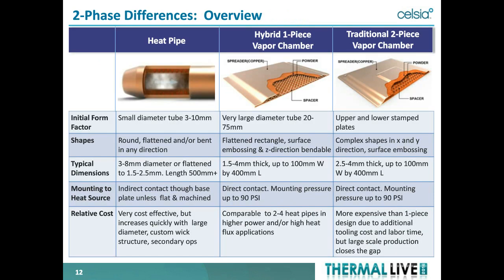What is the difference between heat pipes and vapor chambers? Heat pipes are round, generally available in 3 to 10 millimeter diameters — though for power electronics, 20 to 25 millimeter diameters are not unusual. Then there are two types of vapor chambers: a hybrid one-piece vapor chamber made from a large diameter tube, and a traditional two-piece vapor chamber where two stamped pieces have wick structure installed, then are sealed and welded around the periphery. Typical dimensions, mounting methods, and relative costs vary between these options.